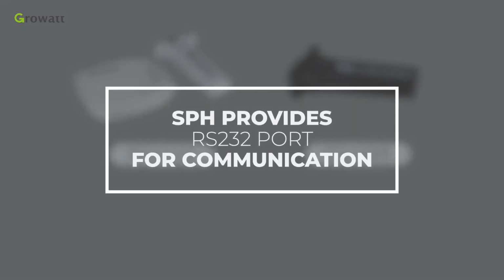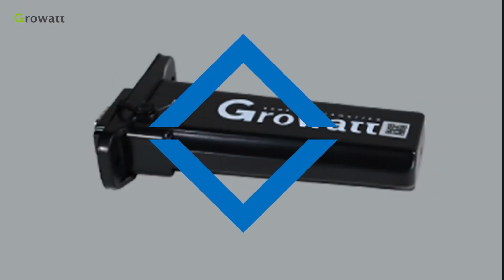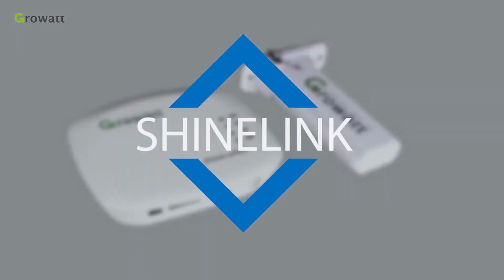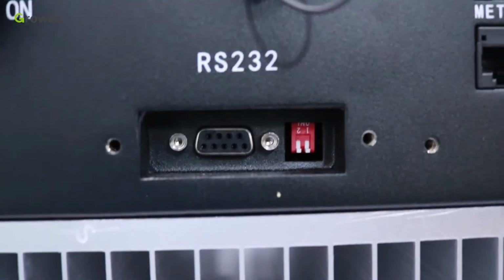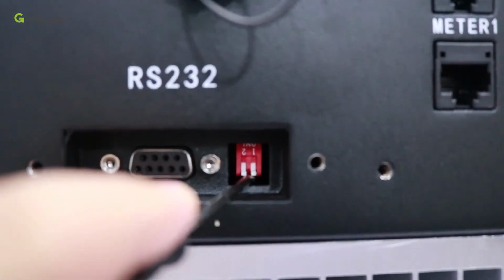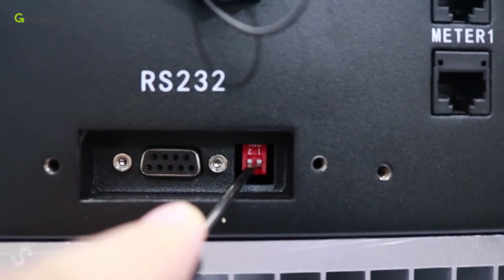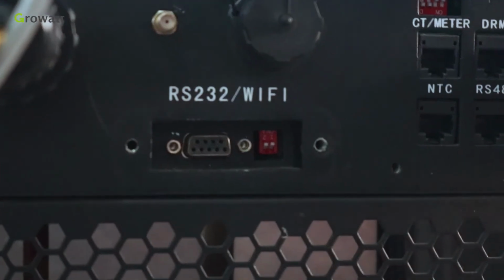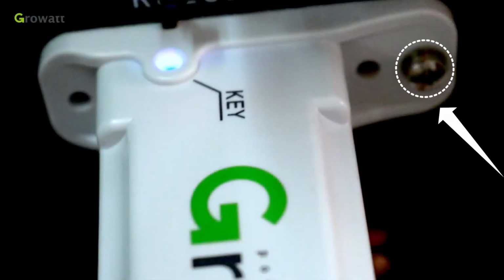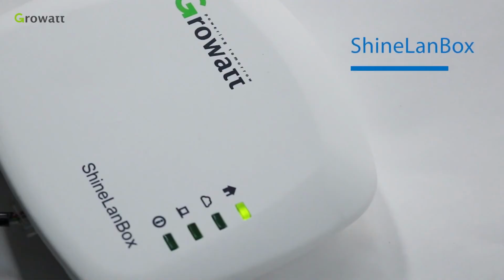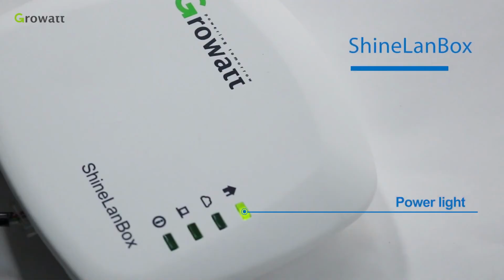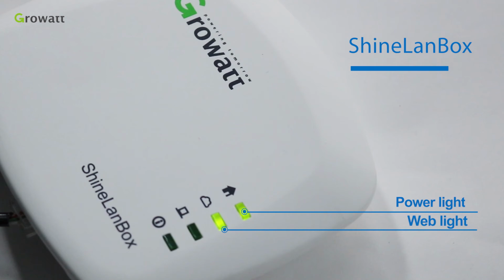SPH provides the RS-232 port for communication. The whole energy storage system can be monitored via Shine Wi-Fi and Shine Link. Firstly, turn the pin 1 and pin 2 to on before connecting Shine Wi-Fi or Shine Link to RS-232 port. For Shine Link, plug the Shine Link stick into the RS-232 port and tighten it by screw. Power the Shine LAN box and use Ethernet cable connected to the router internet. When the web light is flashing, it means it's connecting to the router, and being on means its connection is successful.